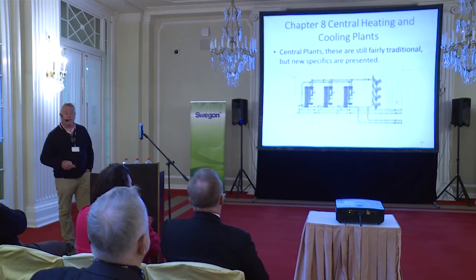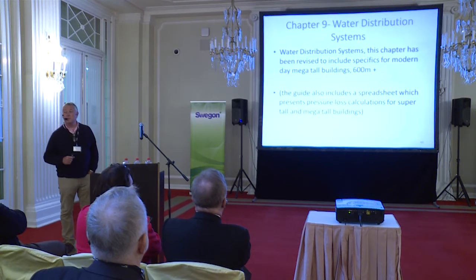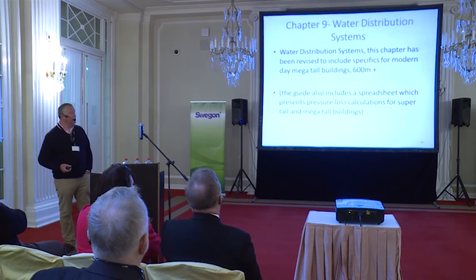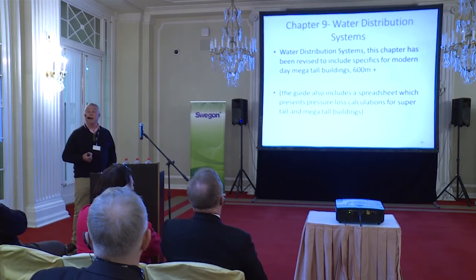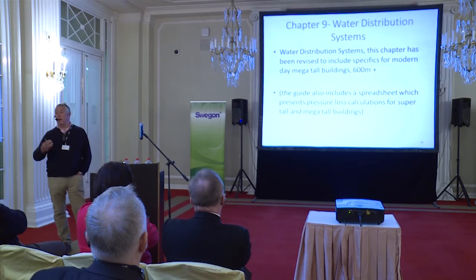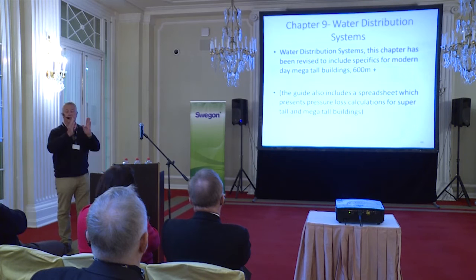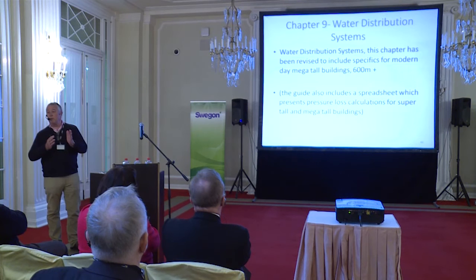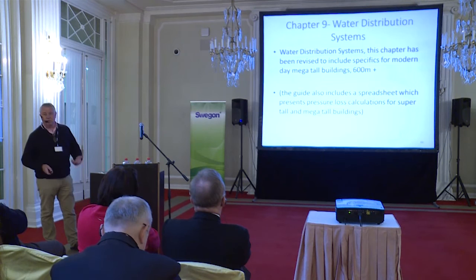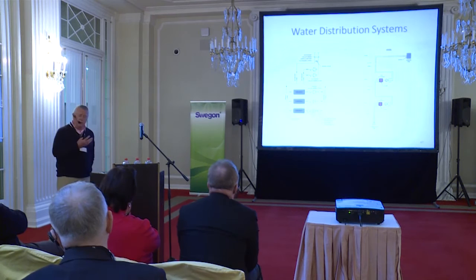This is where we've been looking at it from the water distribution system, because we all learn the hard way that when we have our valves in the system, there's only a certain amount of pressure, so many kPa you can have on the valve, or it starts bursting through the valves. So if we know and look, everything's fine if you keep the pumps running. As soon as you turn the pumps off, then you have two columns of static water coming down. So if you start working out what the pressure would be of a 600 meter high building on the static pressure, you know full well it's going to exceed the maximum capacity that your valves and fittings are going to have. So what we then do is we have to split the building up with pressure breaks to get up there.